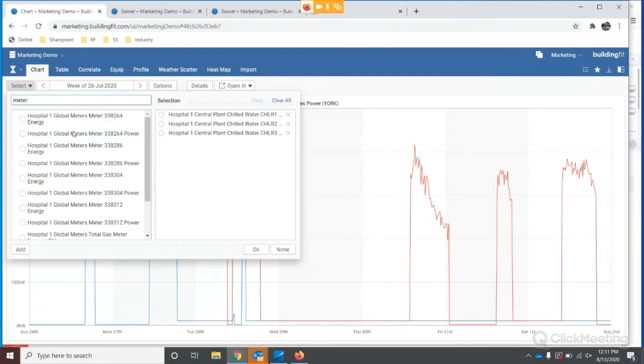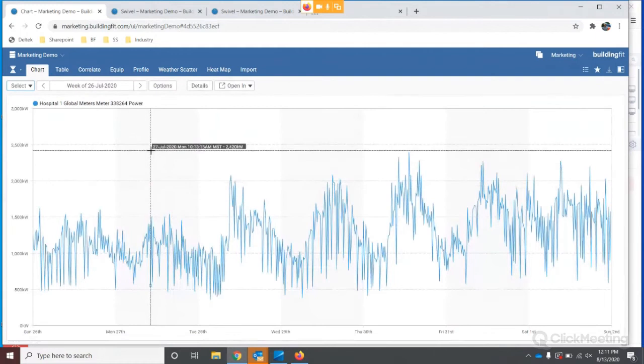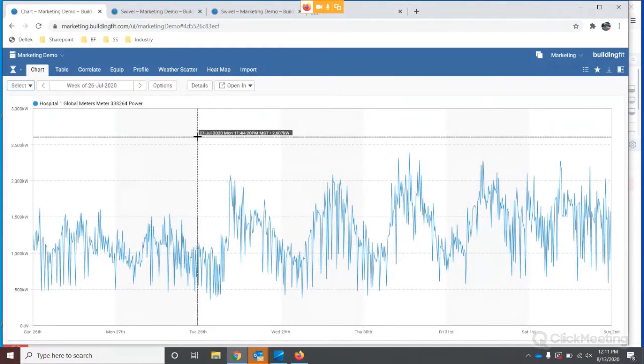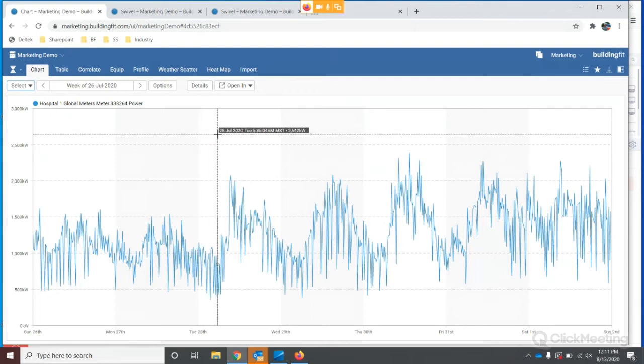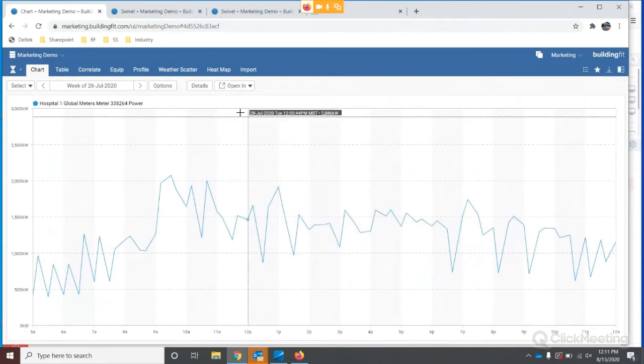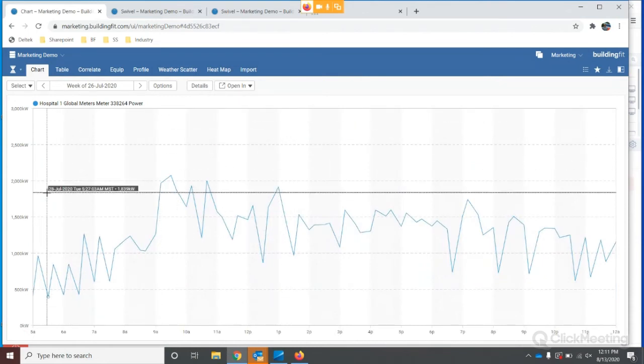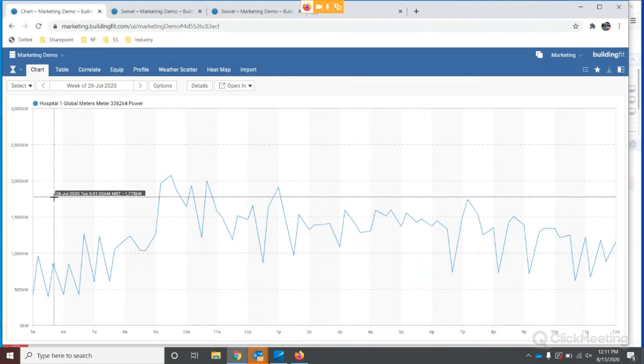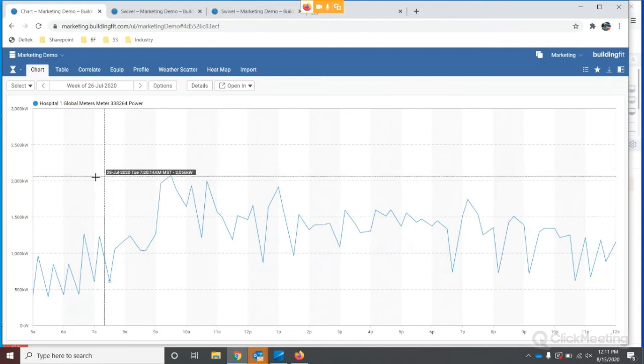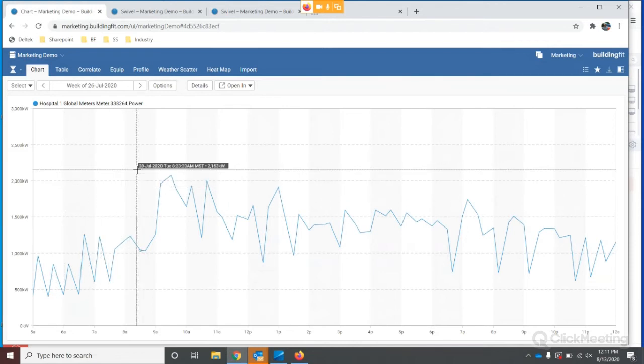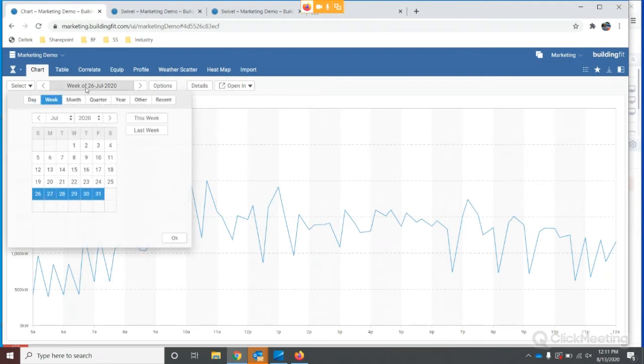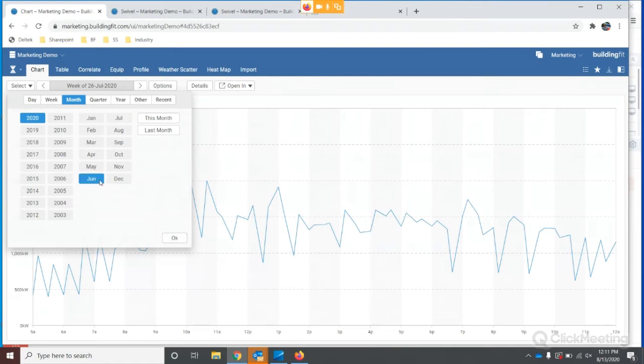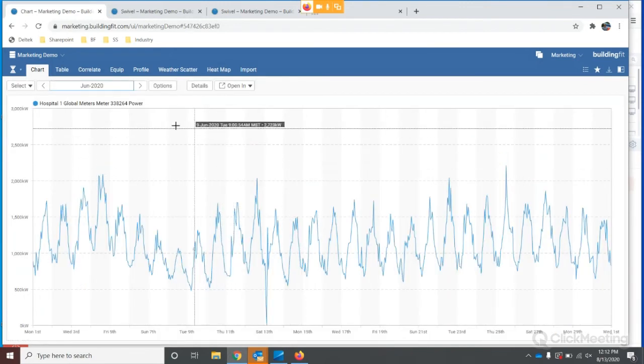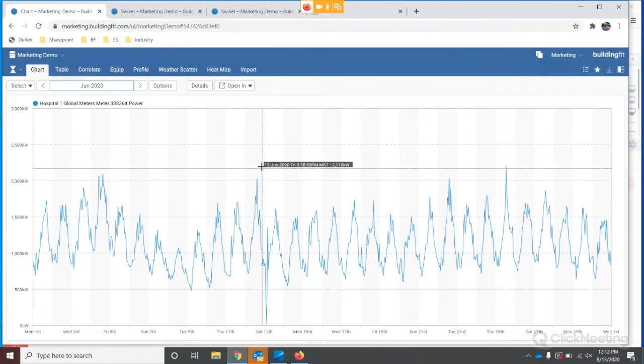Now just rolling it up to the meter level—it's not just for points on a building automation system, we're looking at power. You can drill down to get super granular down to a point on an individual piece of equipment, or zone in on a period of time during a day. That's useful not just for diagnosing issues in a facility, but also for diagnosing things like different energy tariffs—we can look at how demand responds over time during a day. If your demand charges were super high last month, you can go back and see what actually happened, say in June. If one day specifically drove that demand, you can look at the equipment specifically. So we're diagnosing just with historical data.